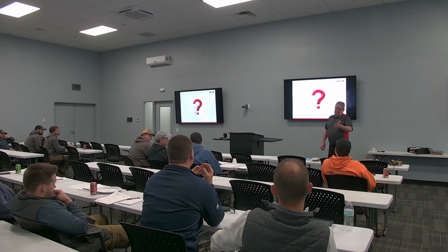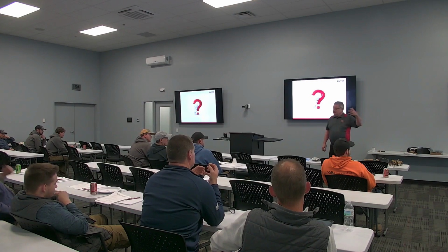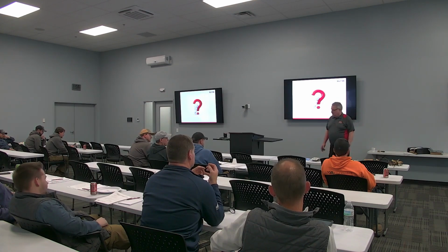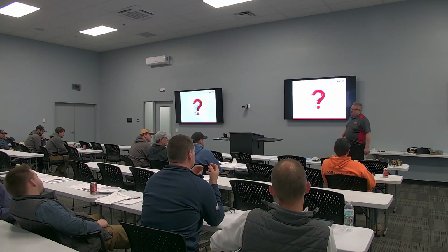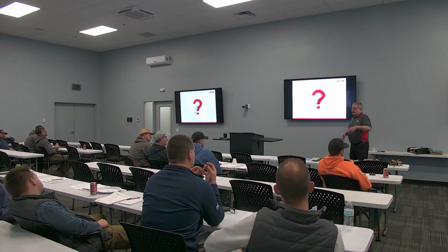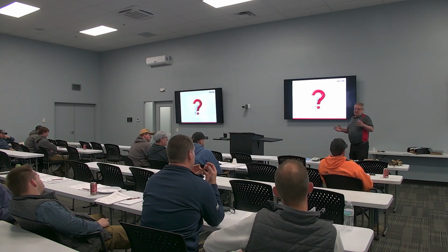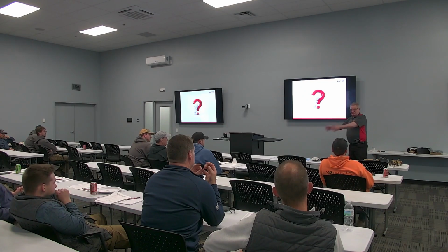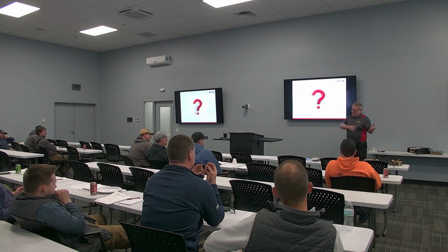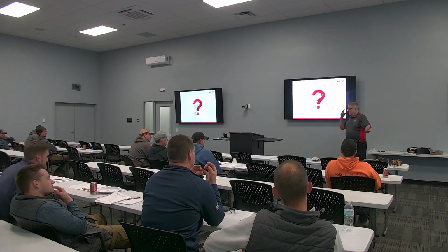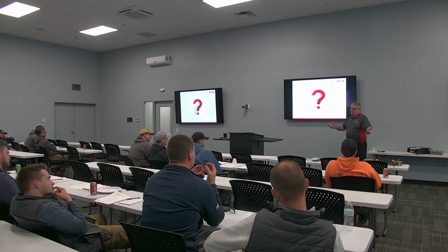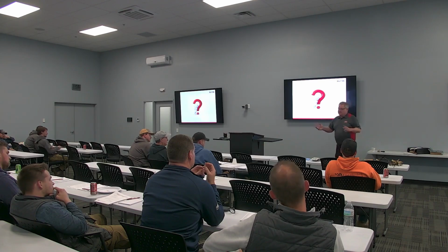Mini split condensate pumps are under the cover of that unit, so those are A2L rated. I guess they haven't changed them; they just got them rated. Compressors are different, so they say. Honestly, I think the compressors are probably pretty similar, but one is rated for A2L and says A2L on it. You can't use the 410 compressor. TXV, same thing. You've got a 410 TXV, an R454B TXV, and an R32 TXV.